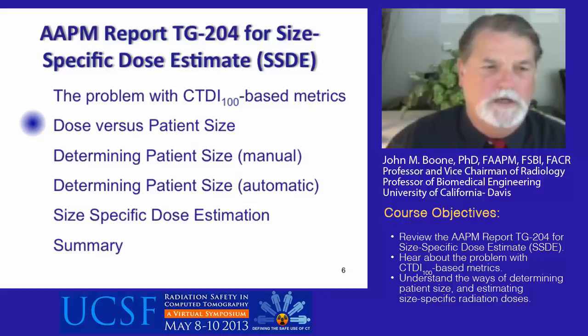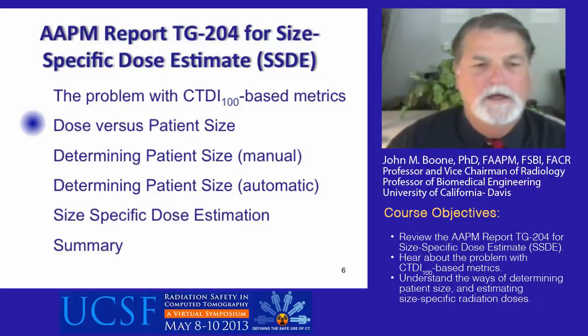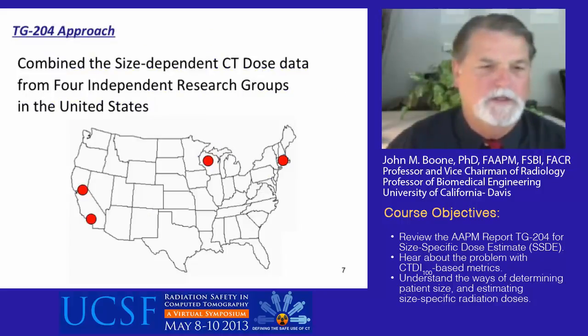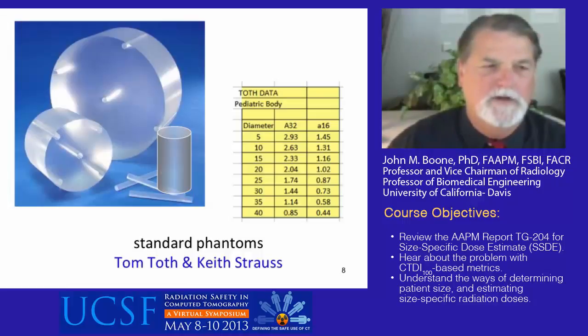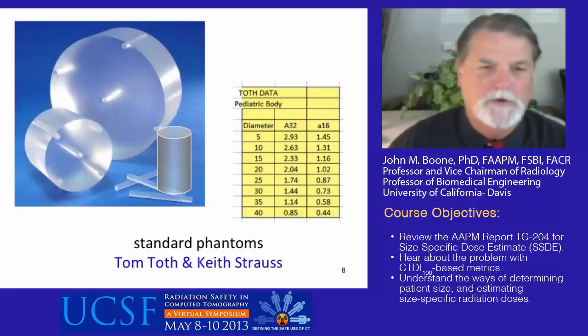Looking at dose as a function of patient size, this effort was a meta-analysis of data produced independently by four research groups, as seen on slide seven. These groups included Tom Toth and Keith Strauss from the Boston area, who used three individual CT-CTDI-like phantoms for their measurements and did very comprehensive, measured data.